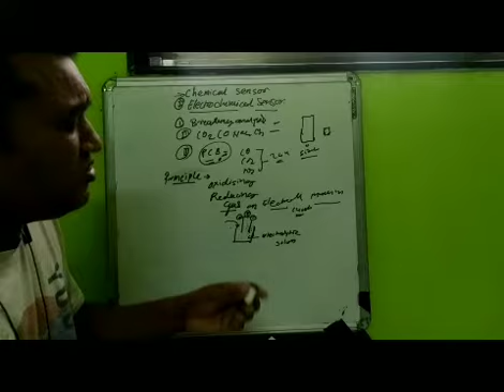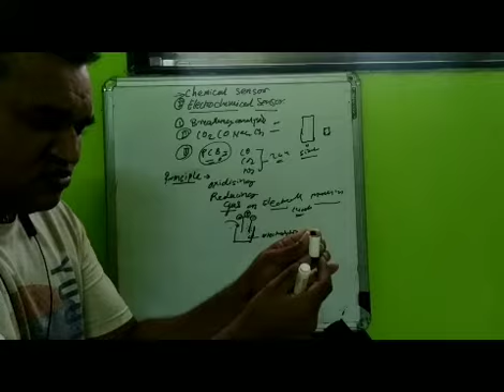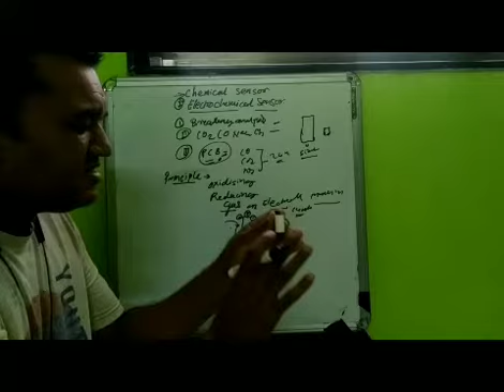So the sensors are like this. Suppose this is the sensor size. In these sensors, two electrodes are inserted in small quantity, one is the cathode and one is the anode, and also a small micro voltmeter, and also the electrolytic solution. When any gas comes from the atmosphere into this sensor, it is mixed with the electrolyte solution. The gas, CO2 or other gases, are deposited on the cathode and anode. Then there is oxidation or reduction of the gases, and currents flow. By measuring the current, we measure the quantity of that gas present in the atmosphere. So this is the principle of the electrochemical sensor.